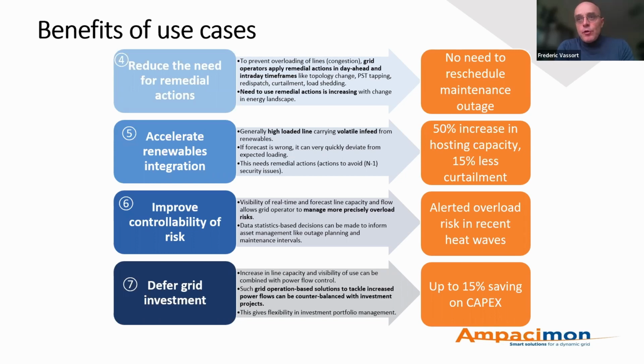It's important to do all of this cautiously. Dynamic line rating is by design a monitoring technology, with sensors constantly measuring key parameters of overhead lines. This actually improves the controllability of the grid and reduces risk, giving real-time visibility of parameters that typically limit line capacity. In summer, on hot days, we've seen examples where the rating is actually lower than nominal. So even if you don't gain capacity in these cases, you gain safety, which is equally important.